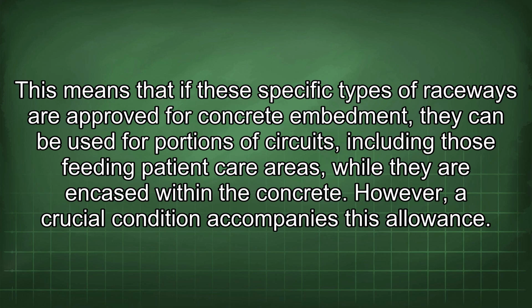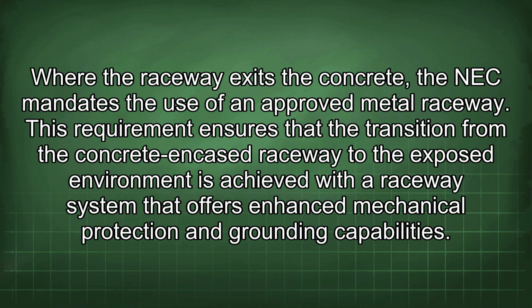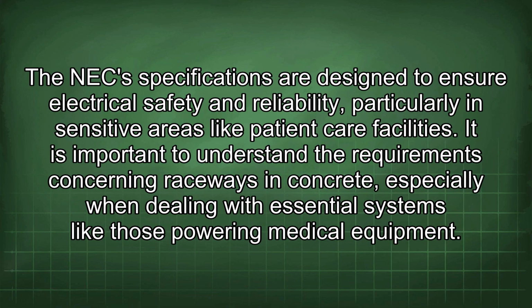However, a crucial condition accompanies this allowance. Where the raceway exits the concrete, the NEC mandates the use of an approved metal raceway. This requirement ensures that the transition from the concrete encased raceway to the exposed environment is achieved with a raceway system that offers enhanced mechanical protection and grounding capabilities. The NEC specifications are designed to ensure electrical safety and reliability, particularly in sensitive areas like patient care facilities.